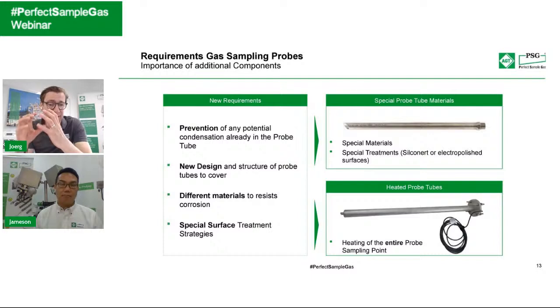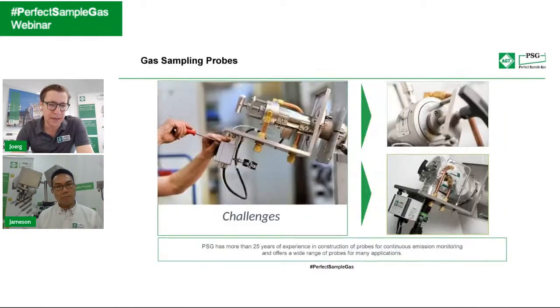You can heat the probe body, the probe itself, as much as you want, but if there's already condensation coming from the probe tube, from the process, you will not be able to handle this in a proper way, right? Yeah. So maybe also a quick fix idea if something occurs there. I mean, it's two different parts. The heated probe tube needs a temperature controller and will be operated to whatever temperature is needed, up to 200 degrees C if this is possible. And this could also be an idea if someone sees bigger problems there in the primary probe cell.